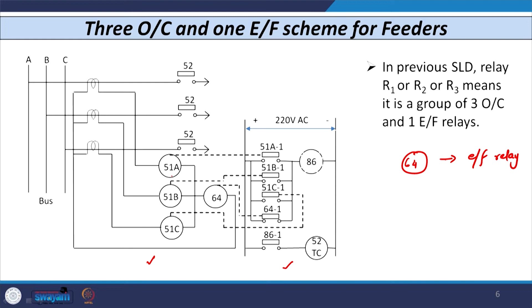The 64 relay has its contact 641. We also have relay 86, the auxiliary relay coil, with contact 861, and then 52TC, the trip coil of the circuit breaker. Now let us see how the three overcurrent, one earth fault scheme works under normal conditions, double line fault, or triple line fault.